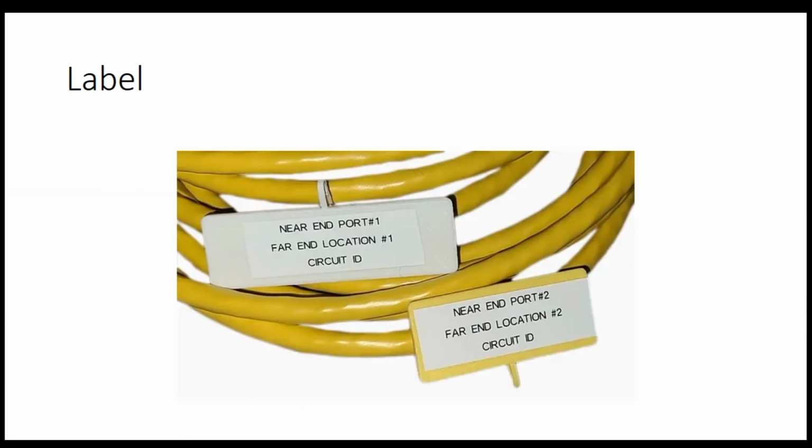Labeling. In general, for labeling inside the data center, we have a labeling scheme for facility equipment, bus cables, and device systems, and a scheme for IT hardware and cables, and there are standard, most commonly used labels for both of them. MV means medium voltage, GN generator, MDB means main distribution panel, and so on.